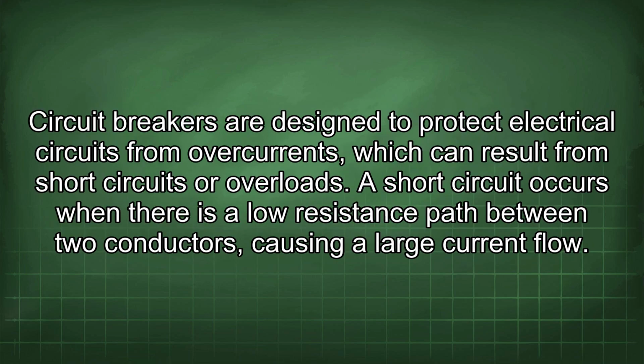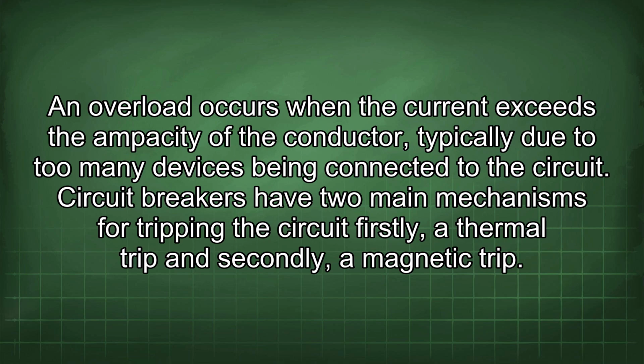Circuit breakers are designed to protect electrical circuits from overcurrents, which can result from short circuits or overloads. A short circuit occurs when there is a low resistance path between two conductors, causing a large current flow. An overload occurs when the current exceeds the ampacity of the conductor, typically due to too many devices being connected to the circuit.